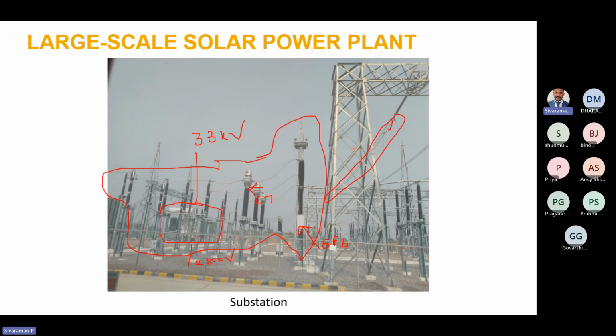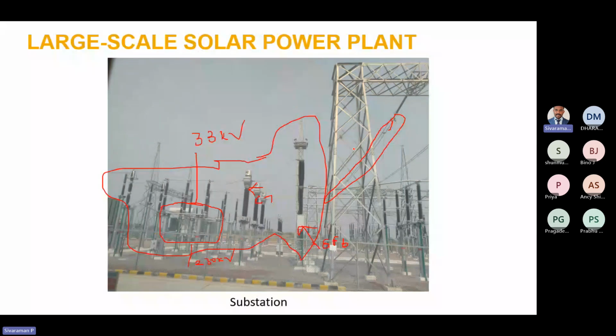So now I came to the end of this presentation on ground mounted large scale solar PV system. I will summarize the presentation. In this presentation, I have explained what a ground mounted solar PV system is, and that in ground mounted solar PV systems we mostly use central inverters. I also showed the single line diagram with an inverter duty transformer of 5 winding, having one HV winding of 12.5 MVA and 4 LV windings of 3.125 MVA.